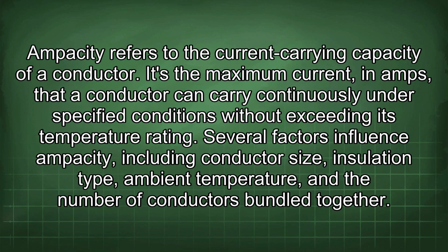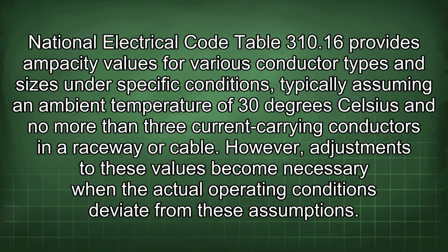Ampacity refers to the current carrying capacity of a conductor. It's the maximum current, in amps, that a conductor can carry continuously under specified conditions without exceeding its temperature rating. Several factors influence ampacity, including conductor size, insulation type, ambient temperature, and the number of conductors bundled together. National Electrical Code Table 310.16 provides ampacity values for various conductor types and sizes under specific conditions, typically assuming an ambient temperature of 30 degrees Celsius and no more than 3 current carrying conductors in a raceway or cable.